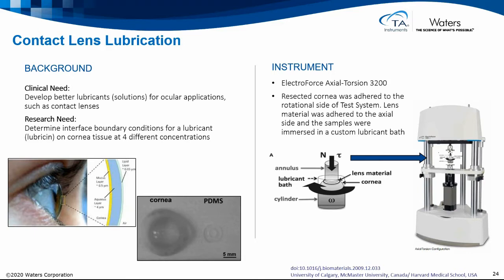So in this study, the resected cornea, you can see in the bottom image there, is actually attached into the lower portion of, actually the upper portion of the instrument. This is a 3200 instrument, kind of like we've seen before, but this one's a little special in that it has a rotational motor, that black part in the middle, and that rotational motor allows us to rotate the lower fixture. So in this case, that lower fixture has the cornea on it.